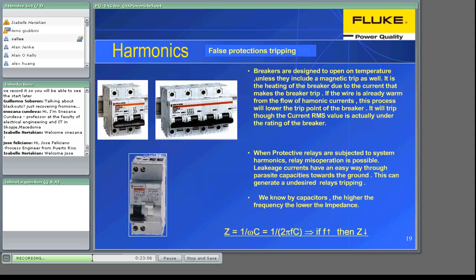Influences on protection tripping. Breakers are overcurrent devices, but it is the heating of the breaker owing to the current that makes the breaker trip. Frequently, the overcurrent rating is too close to the nominal current, maybe because it is underestimated, and the circuit is prone to so-called nuisance tripping, caused by the harmonic content. As for protective relays, the RCD, residual current devices, leakage currents may reach thresholds that cause them to trip.